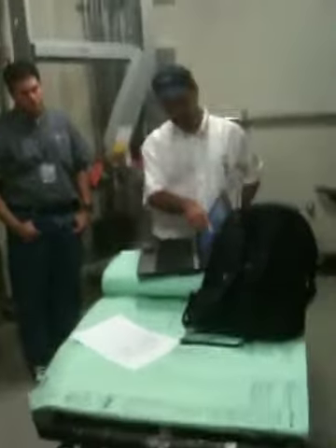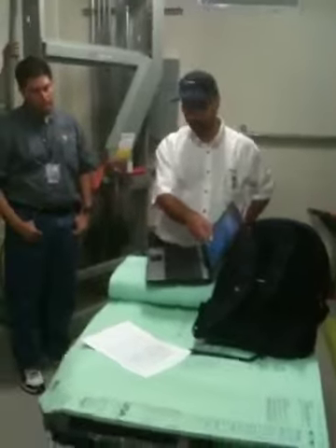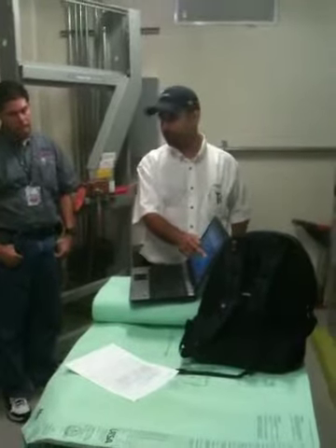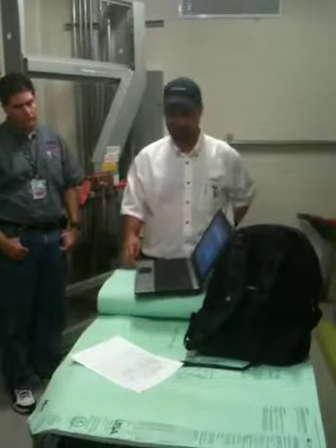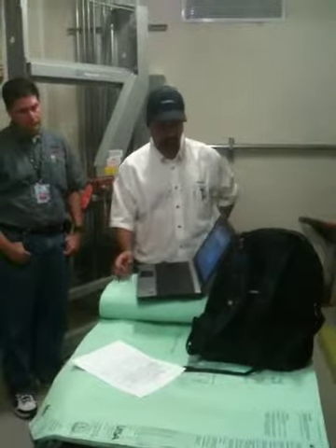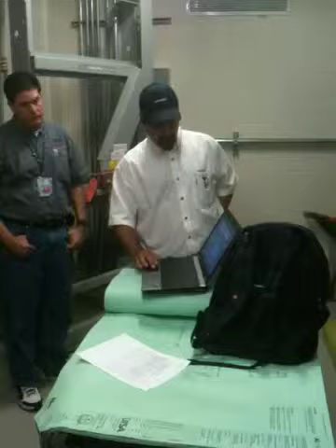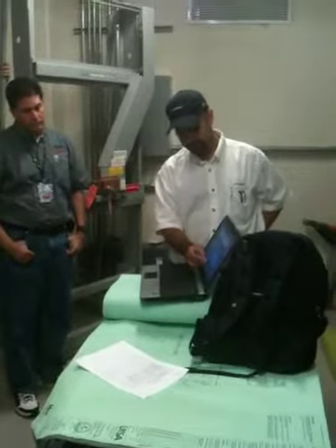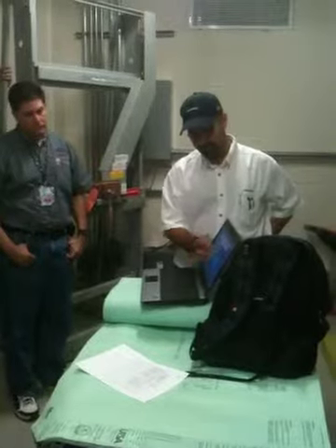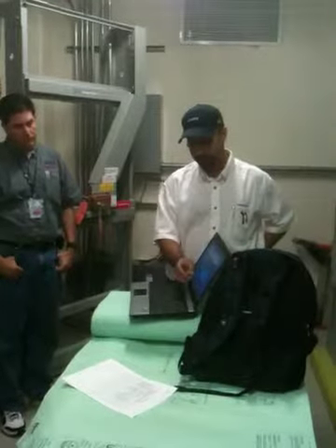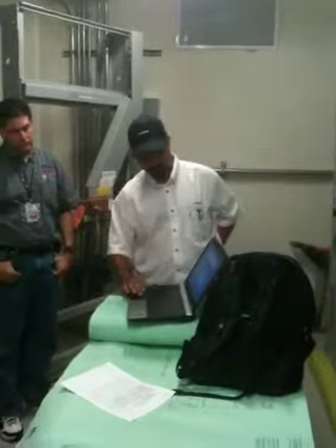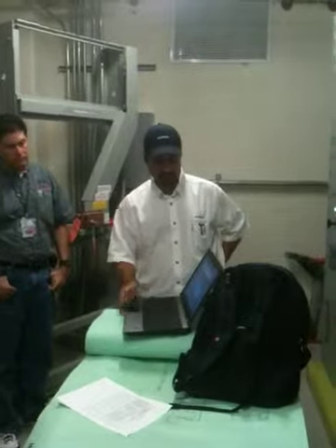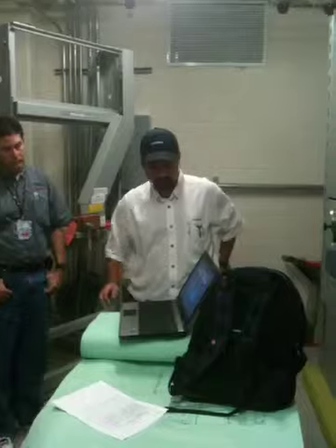In case it's a dual module, which is usually the case for water flow systems, it'll tell you which one of the switches is the one that's active. So in this case, it's switch 1. If you notice, the buttons at the top and the bottom have an arrow pointing up, and they'll light up when you're able to hit them. So in this case, we want to go back, so we hit the back button. It'll take us back to the initial screen.